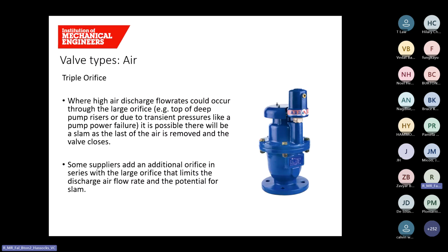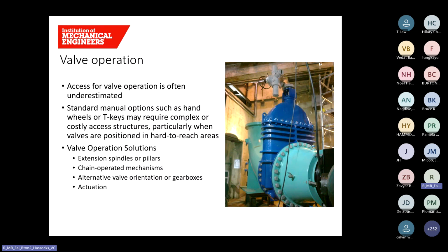The triple orifice air valve is used when a high air discharge flow rate is required and to minimise the risk of surge. When the large orifice closes very quickly, it can cause a surge event. So this valve aims to minimise that effect. So let's talk about valve operation.